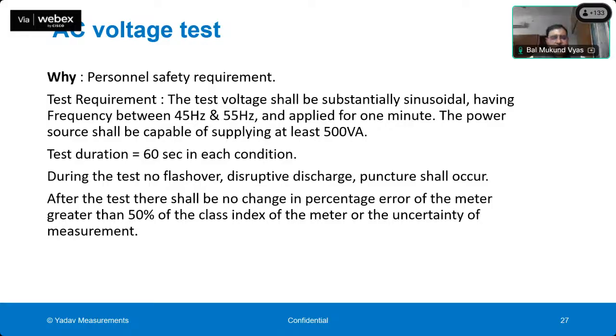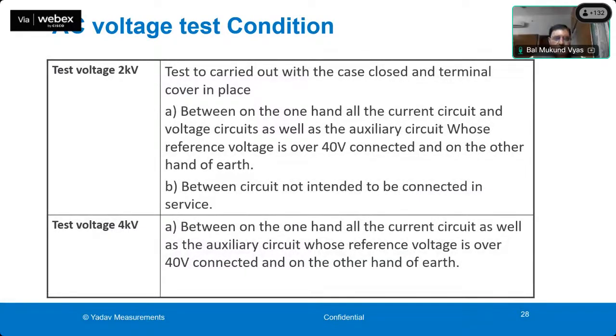So another important test is the AC high voltage test, which is for personal safety, and this test duration is 60 seconds, which is 1 minute. As I told you, if it is a reinforced insulation type of meter, then a 4 kV test is to be applied. But sometimes, if there are rack mounted meters, the meter has an earthing provision. In that case the meter can be tested for 2 kV of insulation, because there is an additional safety measure of earthing. So these are the 2 kV and 4 kV test requirements between other circuits also. If there is a safety SELV circuit, it also has to be tested for insulation.